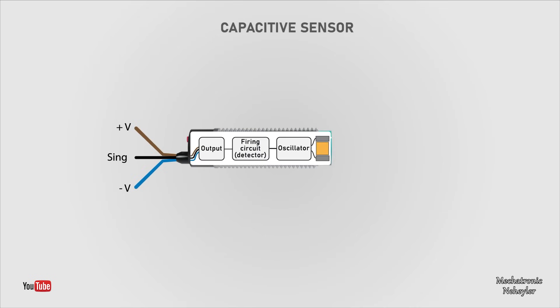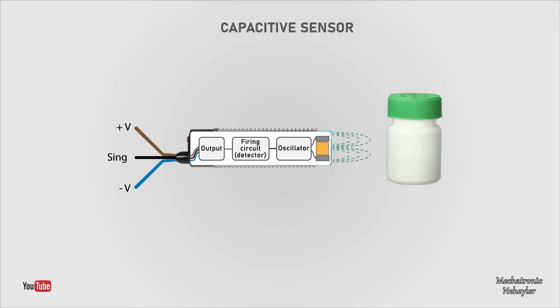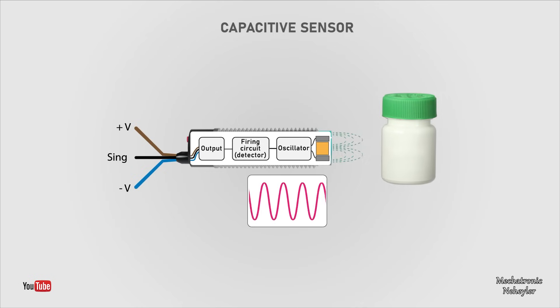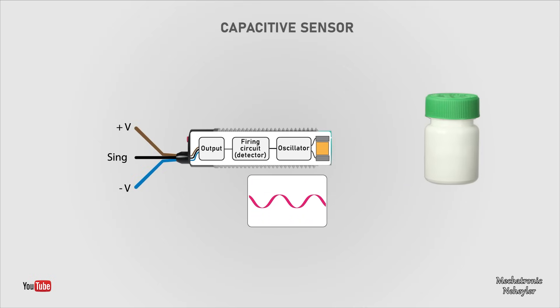Internally, the capacitive sensor consists of dielectric plates with a certain capacitance on the detector face, which emits an electrostatic field. The other important parts are the oscillator, which generates waves at a certain frequency, the trigger circuit, which is activated when it detects an object, and the output, where the signal is digitized. When an object approaches the sensor, it produces changes in capacitance which alter the electrostatic field. The oscillator remains inactive when the object is outside the field, but if an object gets closer, the oscillator moves at maximum frequency and amplitude. If the object moves away, the oscillator returns to its default state.